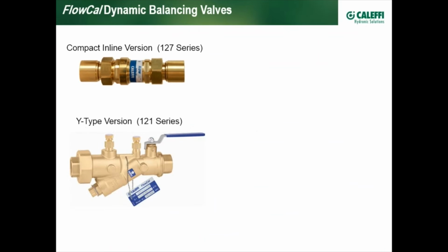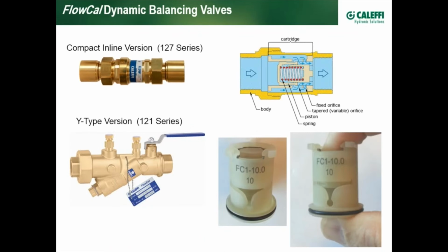Caleffi also makes dynamic balancing valves, but we do something a little bit different. Our cartridges are polymer. They are silent, unlike the metallic cartridges that are most common. They can experience a resonant frequency at certain operating conditions, creating a hum and nuisance noise. So the dampening effects of polymers prevent that from happening. Otherwise, the cartridges work very similar to the metallic cartridges that have been around for some time.